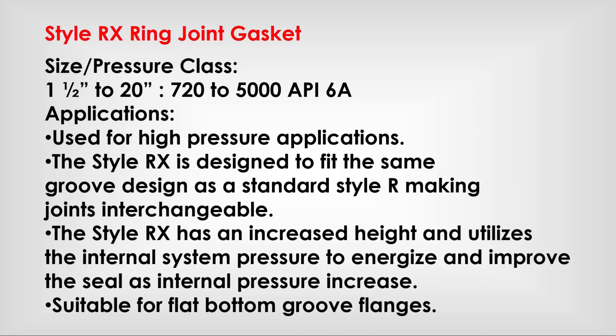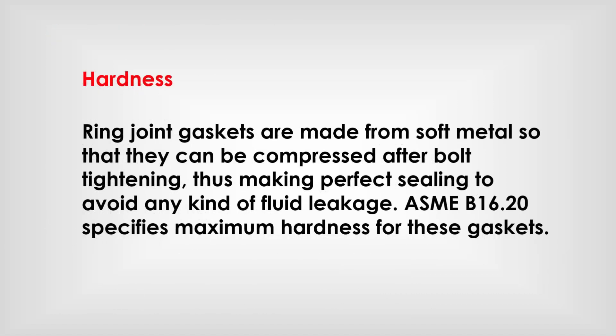Style RX ring joint gaskets: size/pressure class — 1½ inch to 20 inch, 720 to 5,000 API 6A. Used for high temperature and high pressure applications. The style RX is designed to fit the same groove as the standard style R, making joints interchangeable. The style RX has increased height and utilizes internal system pressure to energize and improve the seal as internal pressure increases. Suitable for flat-bottom groove flanges.